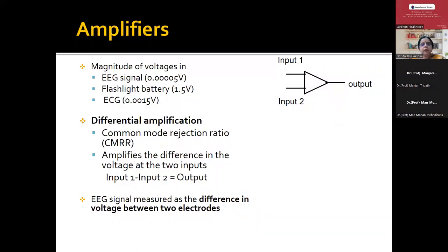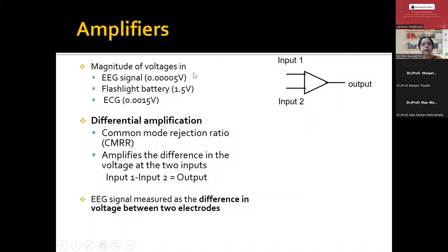What is the role of amplifiers in the EEG machine? Normally when the EEG is generated, it has a very low amplitude — about a thousand times less than the ECG voltage. If you look at electrode one and electrode two, the difference between them becomes the output which manifests the EEG. The amplifiers do differential amplification — the potential difference between input one and input two comes out amplified a thousand times by the amplifier in the EEG machine.